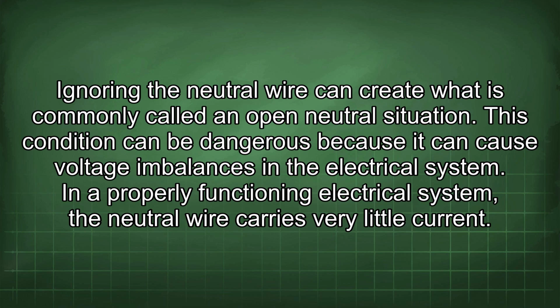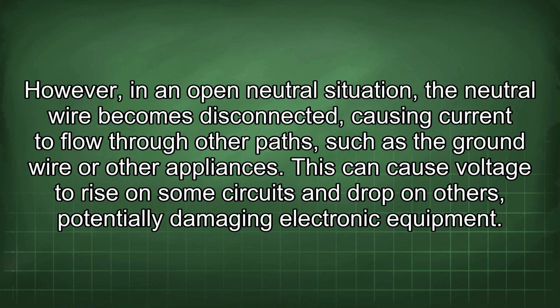In a properly functioning electrical system, the neutral wire carries very little current. However, in an open neutral situation, the neutral wire becomes disconnected, causing current to flow through other paths such as the ground wire or other appliances. This can cause voltage to rise on some circuits and drop on others, potentially damaging electronic equipment.